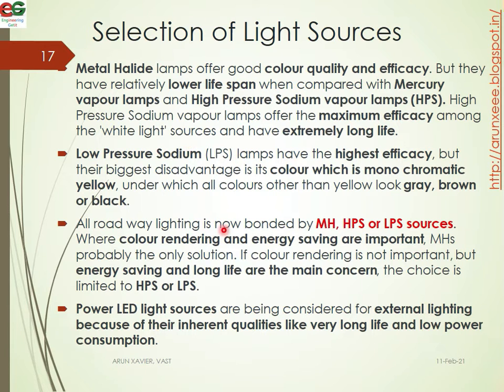All roadway lightings are now bound to Metal Halide, HPS, or LPS sources. Where color rendering and energy saving are both important, Metal Halide is used. If color rendering is not critical but energy saving is the most important factor, HPS is used. Power LED light sources are also being considered for external lighting.